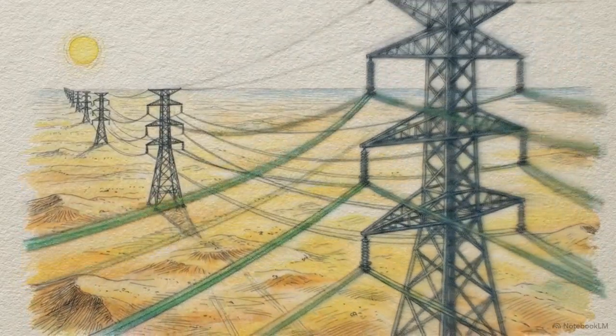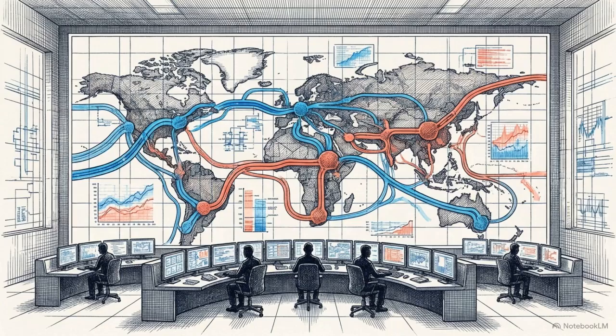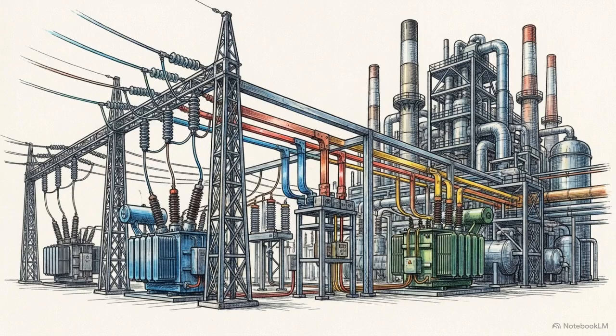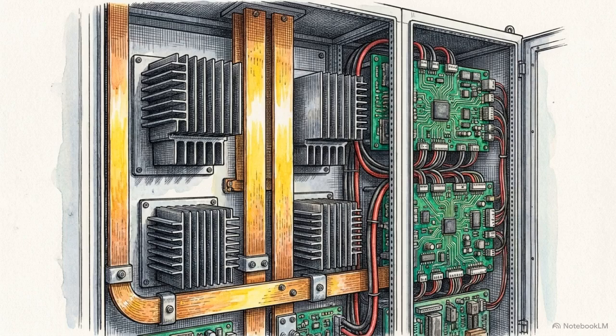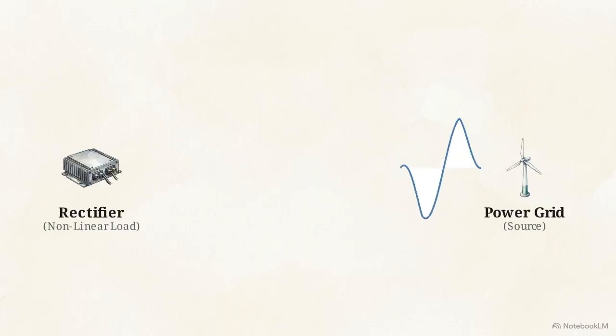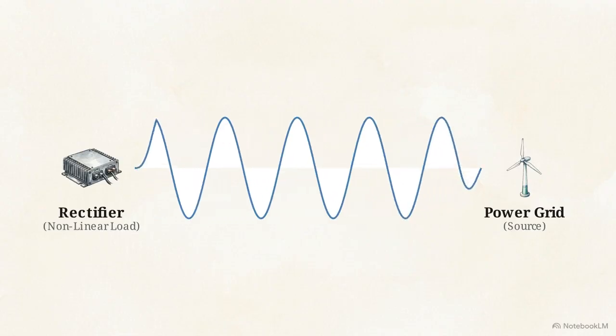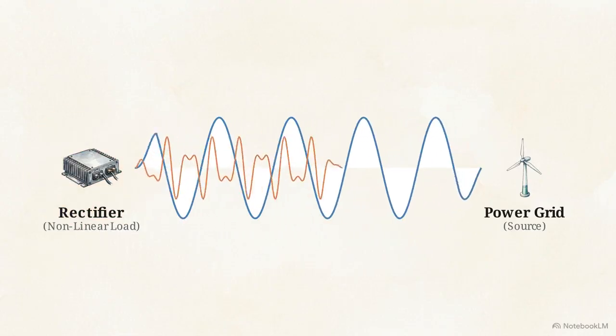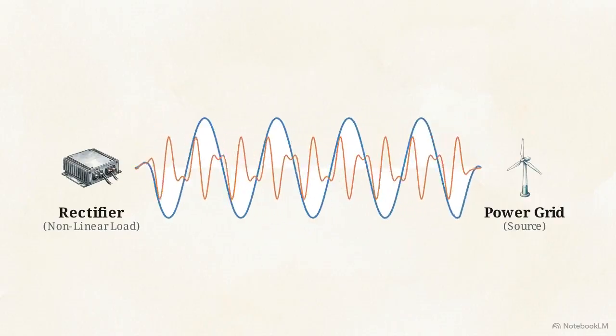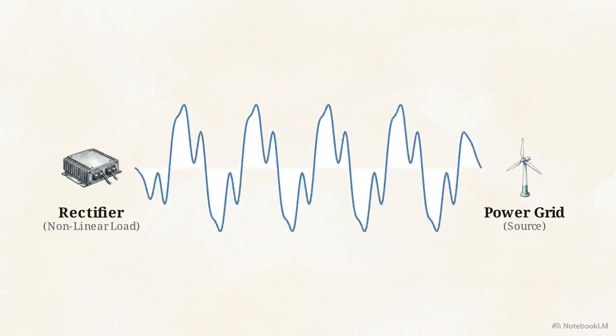Grid operators require both profiles: massive alkaline installations to process large baseloads, and agile PEM arrays to provide rapid frequency regulation. Interfacing either technology with the grid requires massive AC to DC power electronics, utilizing large banks of thyristor or IGBT-based rectifiers. These rectifiers function as immense, highly nonlinear loads on the electrical network. They do not draw power in a smooth, continuous wave, which means they inject severe harmonic distortions back into the power system. The rectifier disrupts the incoming waveform, sending a jagged, distorted signal back upstream toward other grid assets.